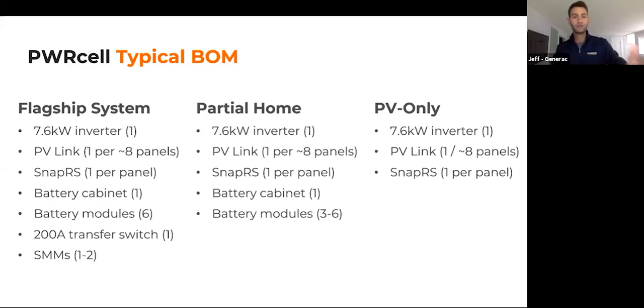A typical bill of materials is available on screen — I'll make a screenshot available for Aaron and Jessica to send out after the presentation. The consistent items across the board are the inverter, the PV Link, and the SnapRS inline shutdown devices, which click onto the negative whip of each PV module. For partial home backup, you have a battery cabinet and variable number of battery modules. For the flagship system: battery cabinet, six battery modules, 200-amp transfer switch, and up to two SMMs. Also coming in late September or early October: an outdoor-rated battery cabinet shipping alongside the three kilowatt-hour Panasonic batteries.